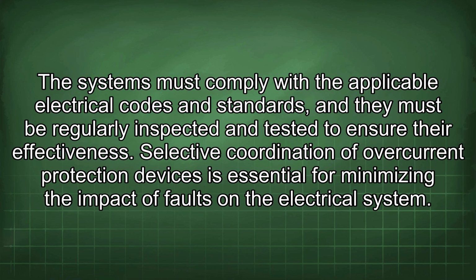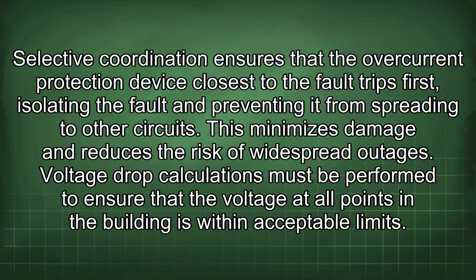The systems must comply with the applicable electrical codes and standards, and they must be regularly inspected and tested to ensure their effectiveness. Selective coordination of overcurrent protection devices is essential for minimizing the impact of faults on the electrical system. Selective coordination ensures that the overcurrent protection device closest to the fault trips first, isolating the fault and preventing it from spreading to other circuits. This minimizes damage and reduces the risk of widespread outages.